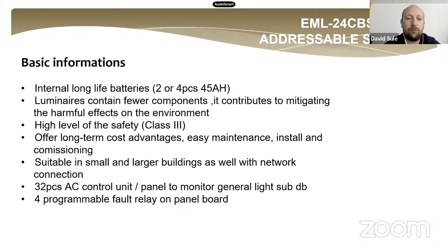All of the panels have 4 free programmable fault relays. That means in the programming software, we can select different events to control the 4 relays. If we want to control the first relay when we have a communication problem with the lights, we can program it separately, one relay to one event, or we can select all of the general fault events to control one relay. And we can program the main panel to be controlled by the slave panels for any fault events, and we can use the main panel relays to be controlled by the slave panels.